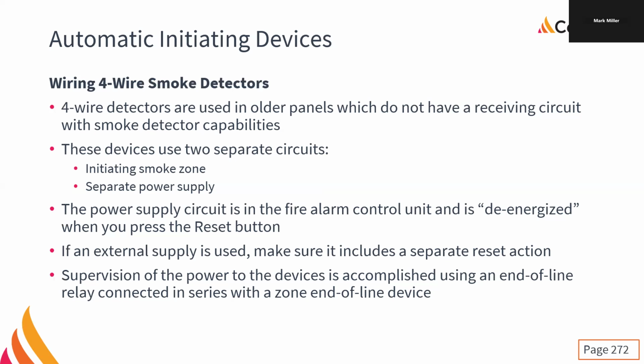But the four-wire smoke detectors, there's two separate circuits there. We have our initiating zone, and we have a separate 24-volt DC power supply. That power supply is coming directly from the fire alarm panel. And when you hit the reset button on the panel, it de-energizes that 24 volts. Because the only way you can reset a smoke is to kill the power to it. Because a smoke activates and it electronically latches in alarm. You hit the reset button and it goes away, which is why you never reset a panel right away if something goes into alarm, even if it's a false alarm, because you need to be able to wander around the zone and find the solid red light, because that's the smoke detector that's gone into alarm.